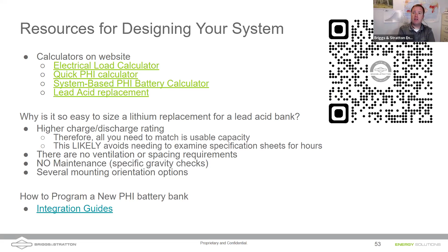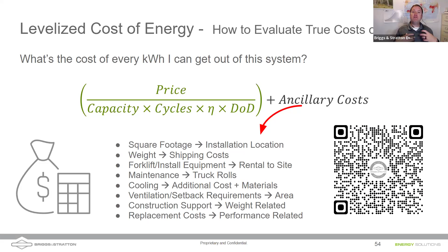It's also important to understand that a lot of people are going to say replacing those lead acid batteries with lithiums is going to cost a lot more upfront, and a lot of homeowners say they just can't do it, so they put the lead acids back. Try to have a conversation and sit down with the homeowner and say, although yes, the lead acids are cheaper to replace, if we come in and put in lithium ion batteries, they last a lot longer. You don't have to water them, you don't need ventilation for the hydrogen gas, and the lifetime cost of these lithium ion batteries indeed is better.